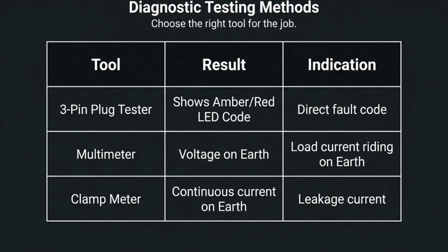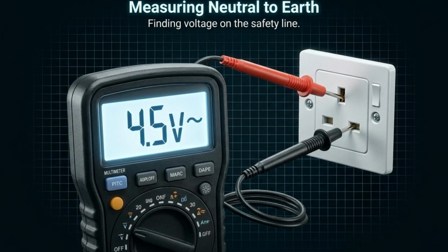To diagnose the issue, you can use specialized tools like a 3-pin plug tester, a multimeter to check for voltage on earth, or a clamp meter to detect leakage current. When measuring between neutral and earth, detecting voltage indicates a problem with the safety line.